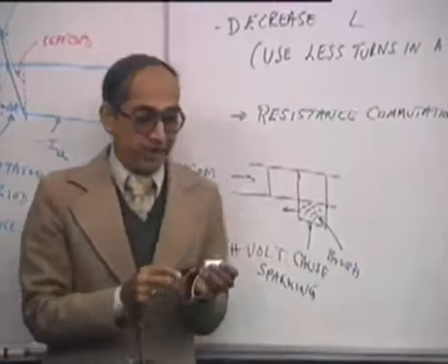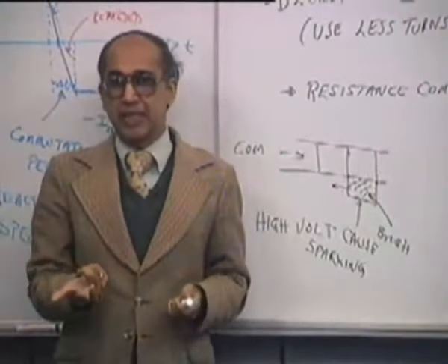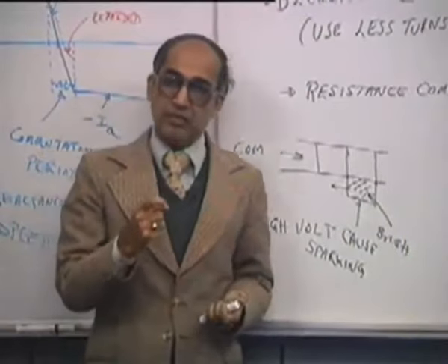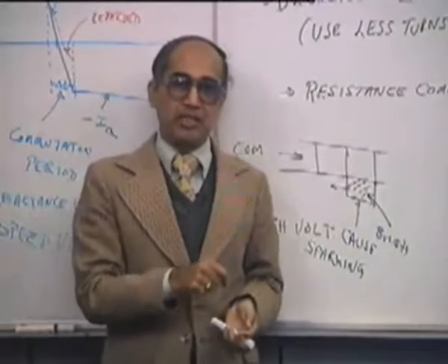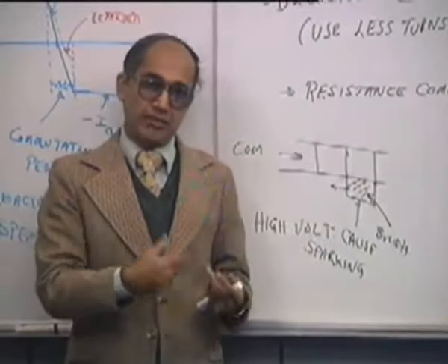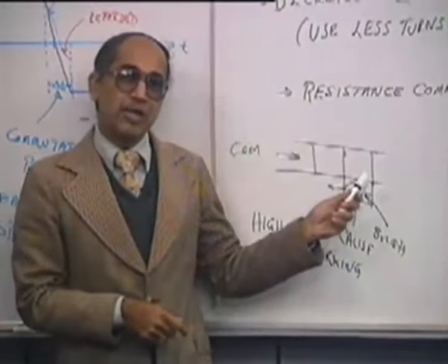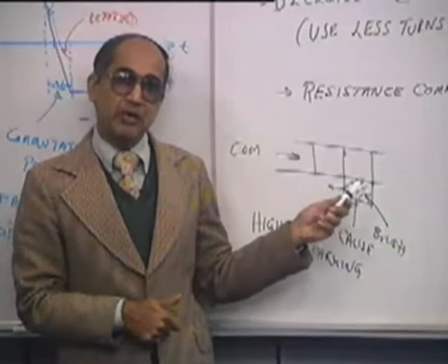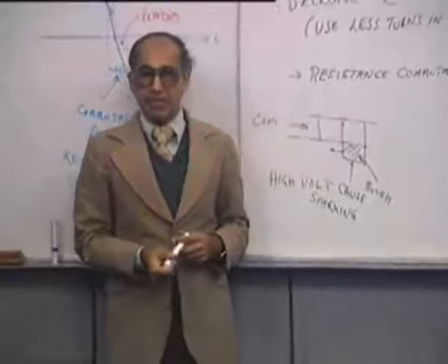So you may often find across the brushes in several DC machines the sparking taking place, and this sparking will have the impact of corroding the materials. That means there will be pits on the commutators, or there could be pits in the brushes. So that will be uneven, that will further result in uneven contacts, and over a period of time it may wear out and necessitate replacements.